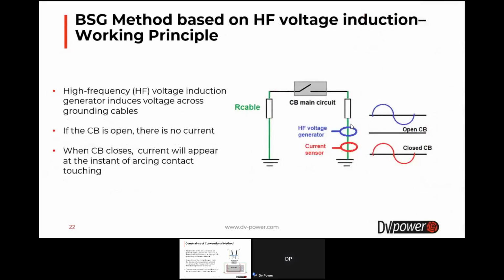So the other main method for both sides grounded timing is based on high frequency voltage induction. The high frequency voltage generator induces voltage across the grounding cables. As you can see, it's a sine wave AC high frequency voltage generator. So if the circuit breaker is in open position, there is no current in the main circuit and the grounding cables, as you can see. But when the circuit breaker closes, current will appear at the instant of the arcing contact touching. The same way, when the circuit breaker opens, the current will disappear at the instant of the arcing contact separation.